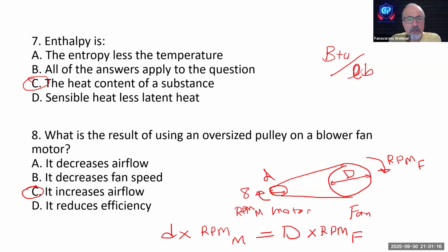So what's happening if this one goes up, the oversized pulley on the blower fan motor? That's right. If this one goes up and everything else is constant, I wanted to know what's happening with the speed of the fan, since it says increasing the airflow. If this goes up and this one is constant, this one is constant, the RPM for the fan goes up.